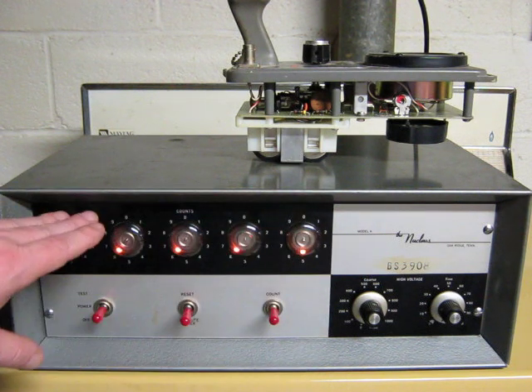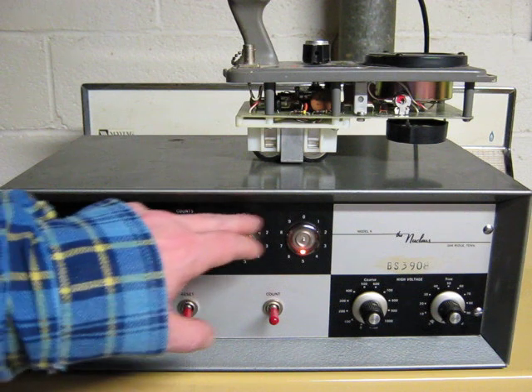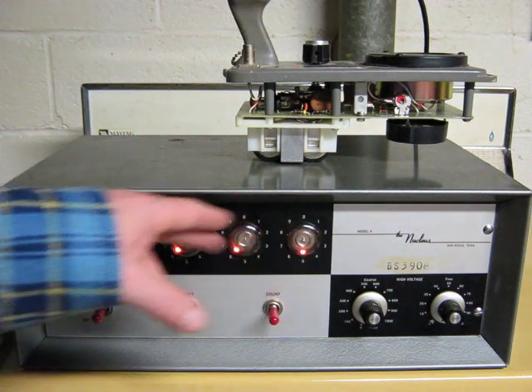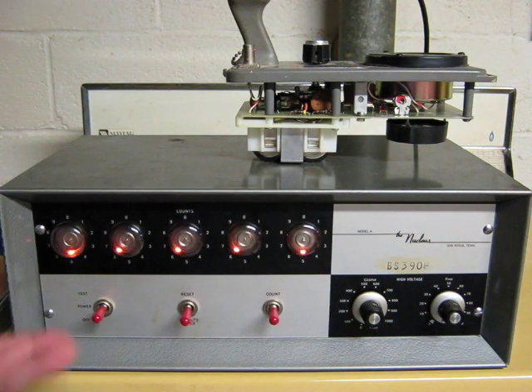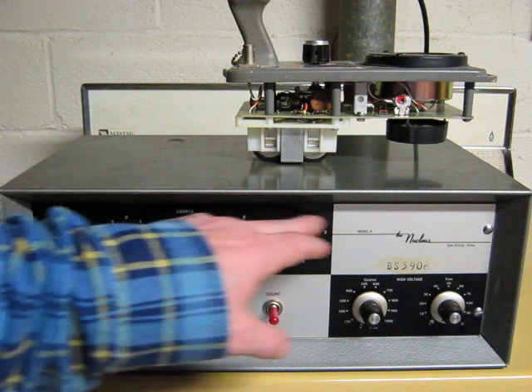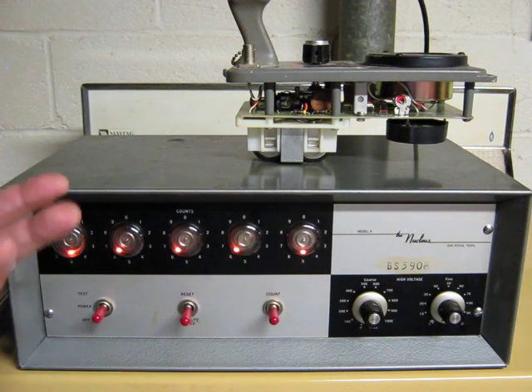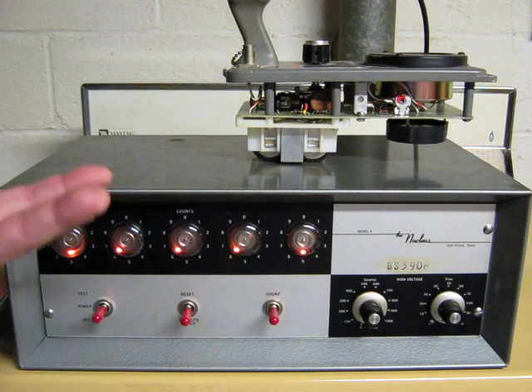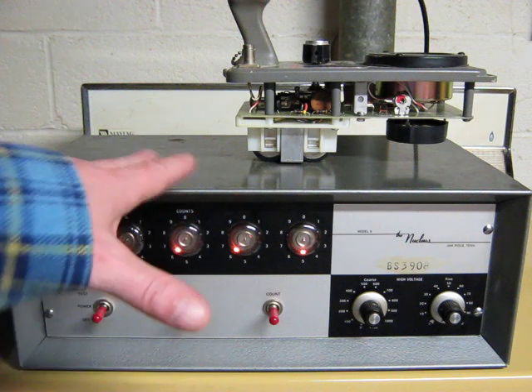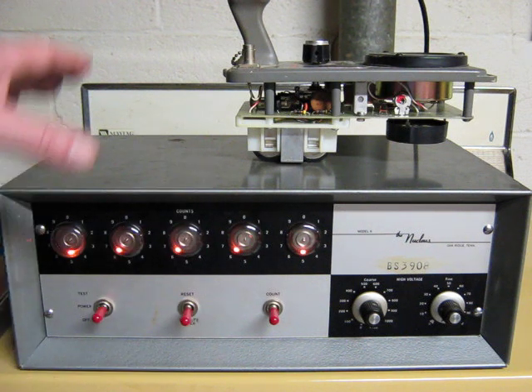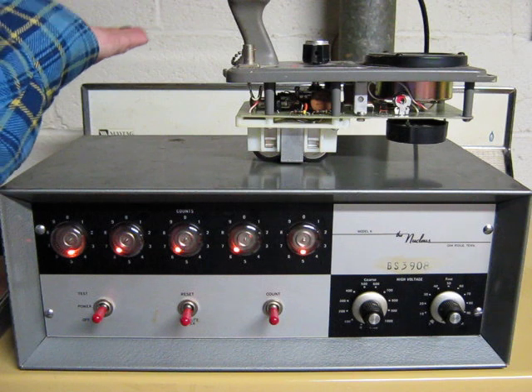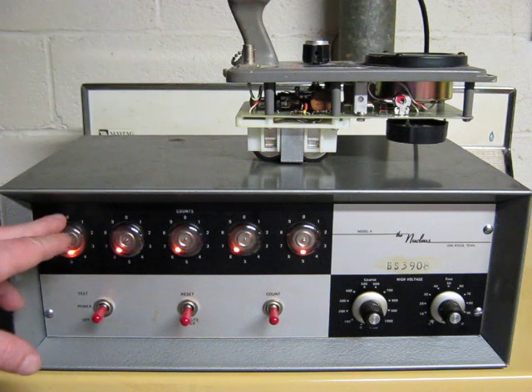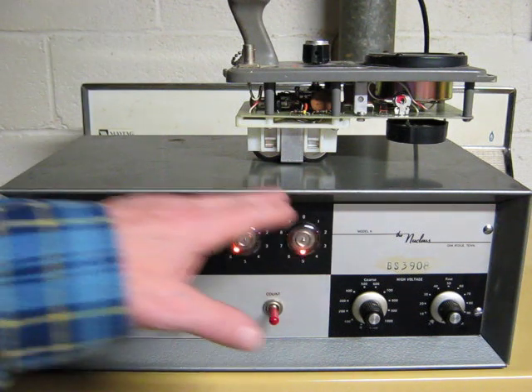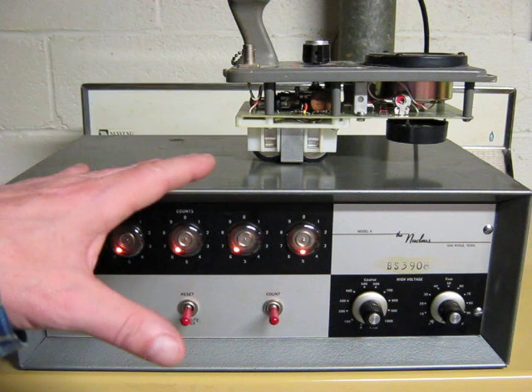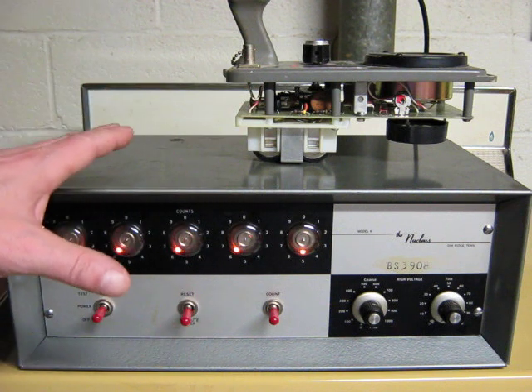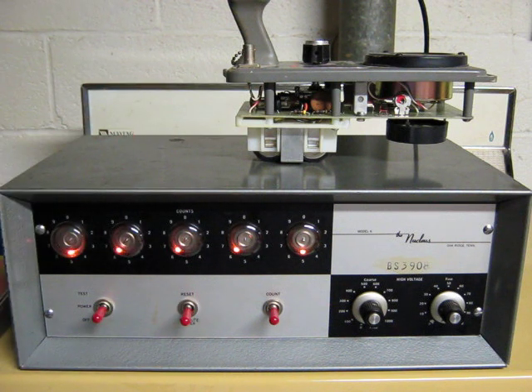So this counter can count to 99,999, or if it rolls over to zeros, well, 100,000. And I guess somebody watching would have to be careful of that. But if you're using a Geiger tube with a radioactive source, and these things roll over past 100,000 in a minute, you need to leave, because there's too much radiation.